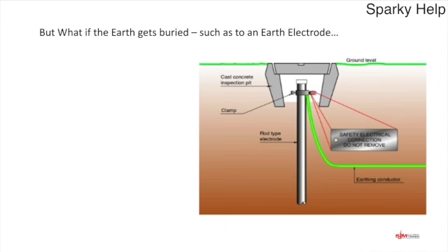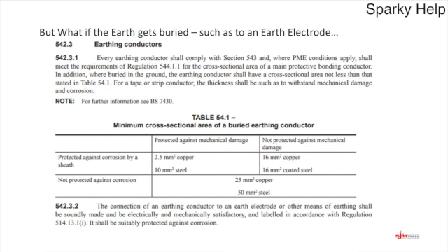But what if the earth gets buried, such as to an earth electrode, as in this example here? The moment the cable gets buried to an earth electrode, that's probably a high resistance in the overall scheme of things, and that would limit the fault current. So it isn't necessarily that you're going to put cables in to carry an amount of current that's going to flow, because there's probably not a lot in comparison to other earthing systems, because this is typically TT. But it's about the fact that you've buried the cable. That is the problem.